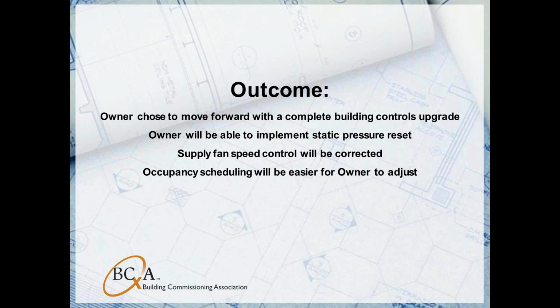So the outcome of this project is that the owner chose to move forward with a complete building controls upgrade. They had the money to spend, and it was a fairly easy sale. With a payback under a 1.5 years, that's a pretty easy sell. They were able to implement the static pressure reset. They will be able to correct the supply fan speed control, which is critical to making the static pressure reset work properly. The owner will have better control of their occupancy scheduling. It's much easier to adjust on the Johnson system than it is in that Niagara system. And they'll have good reliability throughout the building and improved control.